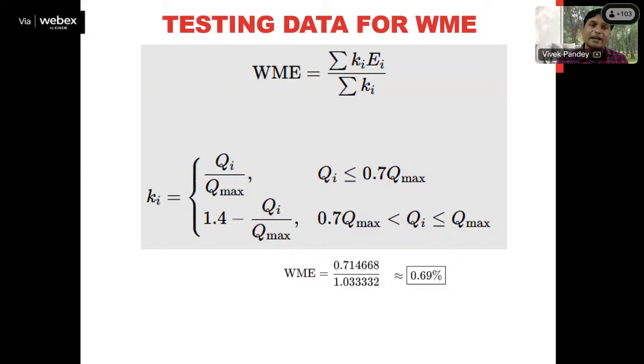You can see here that for Ki, 2 formulas are given. Ki can be calculated either using the relationship Qi upon Qmax, or you can use the formula Ki is equal to 1.4 minus Qi upon Qmax. Whether we have to use 1.4 minus Qi upon Qmax or only Qi upon Qmax depends upon the flow rate or the test point you have selected.